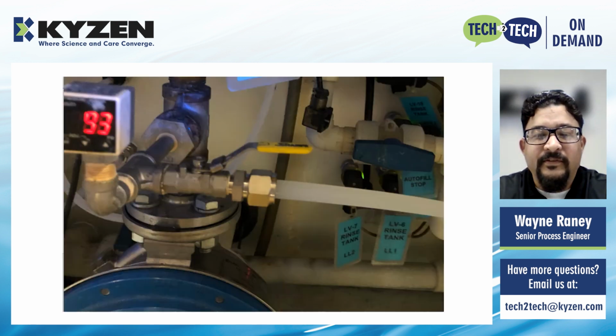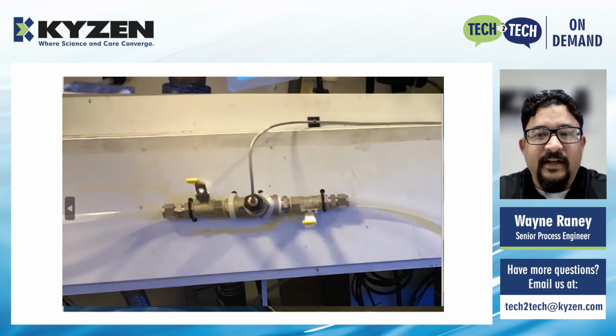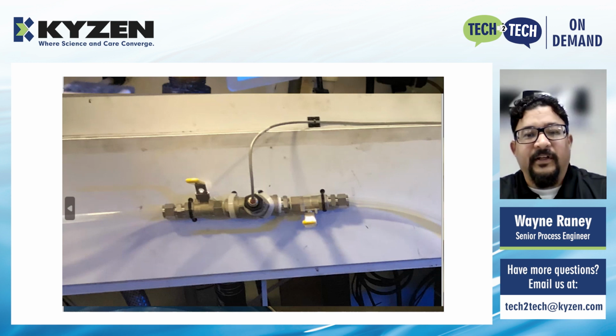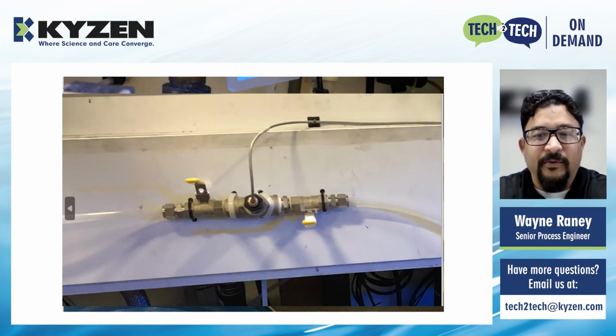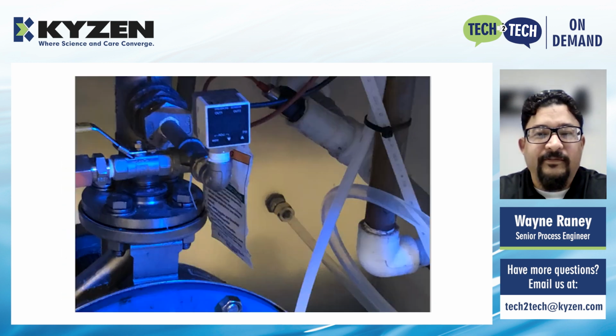So the first thing we do during one of these maintenance periods is that we plumbed on the output of the wash pump a pressure gauge with a valve and tubing, and plumbed the tubing to the isolation valves in the sensor. Here are the isolation valves on either side of the sensor. We made this assembly offline and mounted it to the machine in a space where maintenance could be done easily on the probe. So flow entered from the left and exited to the right. This is where we turn the fluid back from the sensor to the tank.